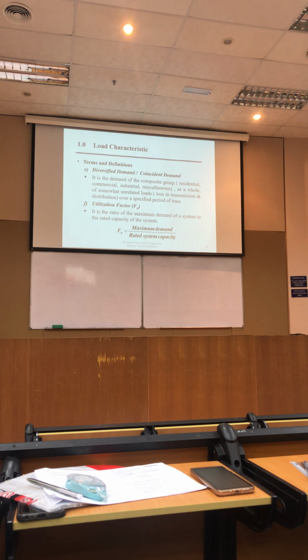We have also the utilization factor. It is the ratio of maximum demand of a system to the rated capacity of the system. So this one is the utilization factor: maximum demand divided by rated system capacity. What is the capacity of the power station? Seperti ini.